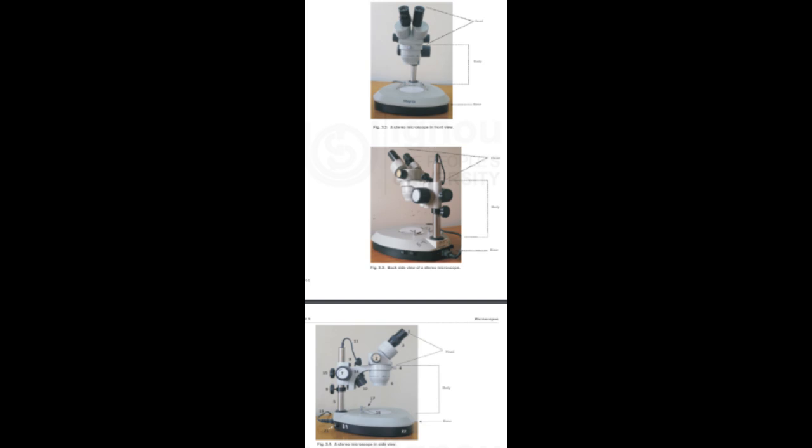Focus knobs, 7, one on either side of the microscope, enable the vertically up and downward movement of the head objective lens unit along the rack and pinion arrangement. The focus knobs also provide for tension adjustment so that even after removing one's hands from the knobs, the focus of the object is not lost. Rack stop, 9, is made up of a collar and a knob which prevent the sliding of the whole microscope assembly from hitting and damaging the stage and the specimen.